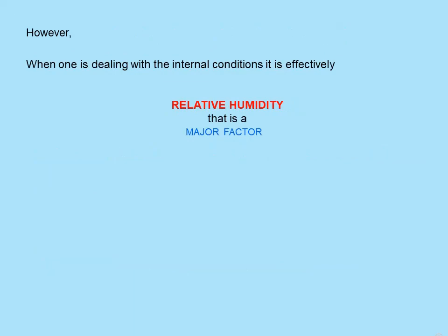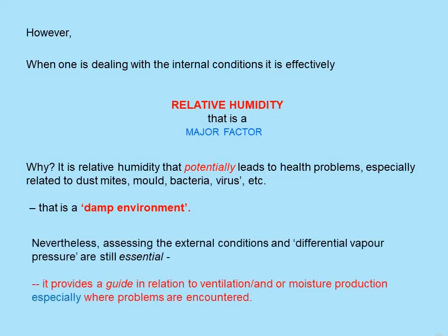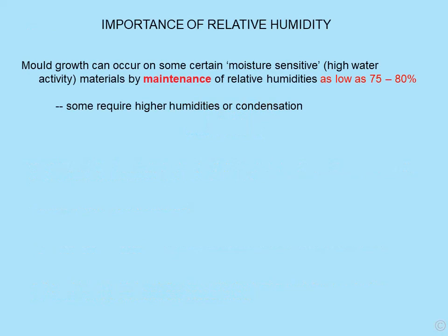However, if you think about it, when one is dealing with internal conditions, in many respects it's effectively relative humidity that is the major factor. Why is this? Because it potentially leads to health problems, especially related to dust mites, mould, bacteria, viruses and so forth. That is what we refer to, in essence, as a damp environment. That's what's caused these problems. Nevertheless, it's still very important to look at differential vapour pressures because they provide a guide in relation to the ventilation and/or moisture production, and this is especially useful where problems are encountered.